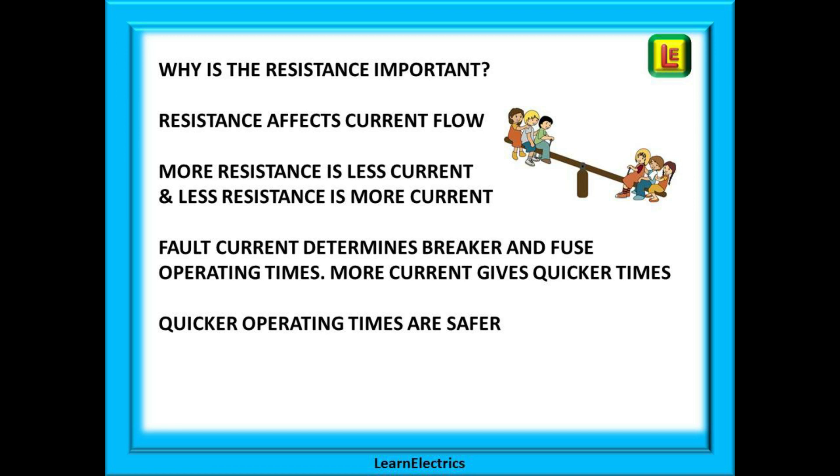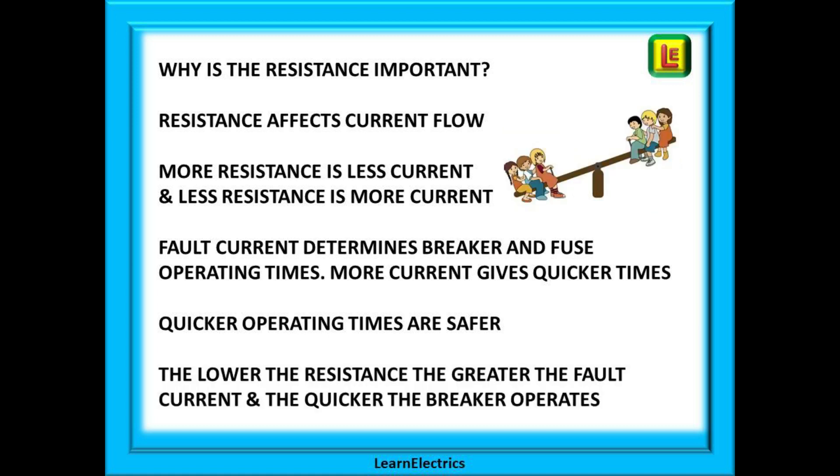It is the fault current that determines the operating time of the breaker or fuse. Ideally we want the biggest possible current to give us the quickest operating time, and to get the biggest current possible we need to have the lowest resistance possible. The quicker the operating time the quicker the fuse blows and the quicker the circuit is made safe. Putting that all together, the lower the resistance of R1 plus R2, the greater the fault current, and the quicker the circuit breaker operates and makes the circuit safe.